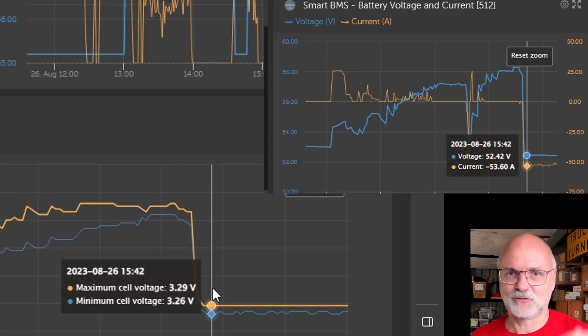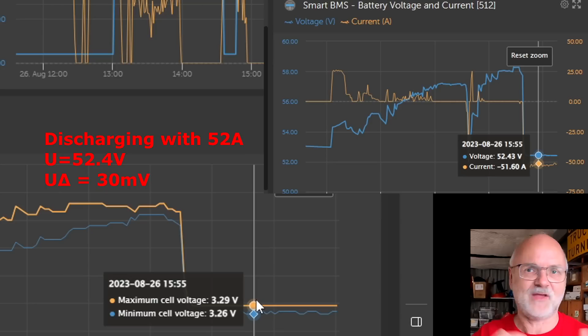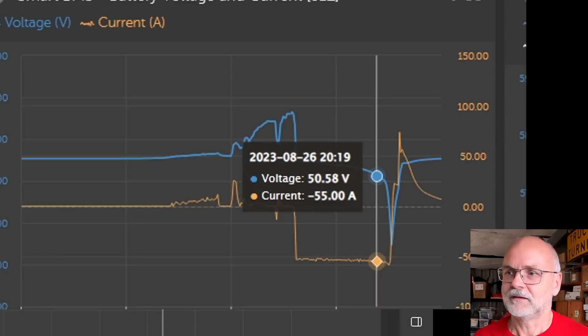So we started right here and the voltage drops sharp into the flat area of the curve, and you can see it's flat, and the cells are coming together regardless if they are balanced or not. You won't see a difference. If we reset the zoom here again and have a look, this is basically our discharge curve.